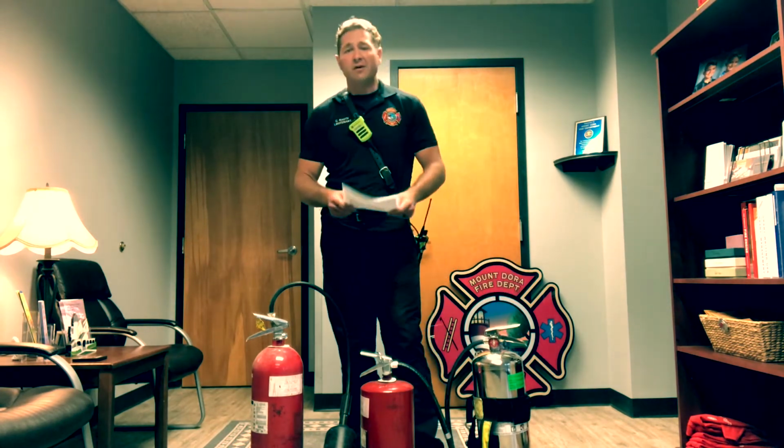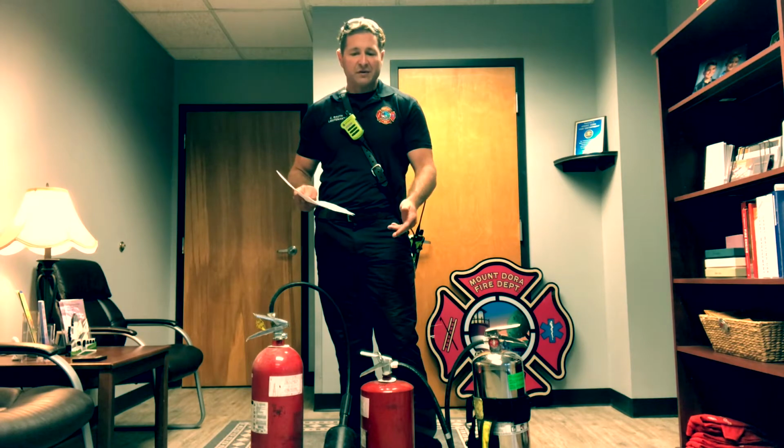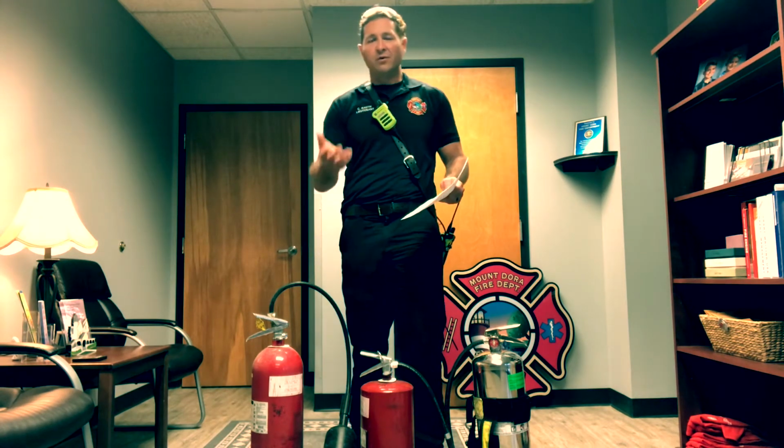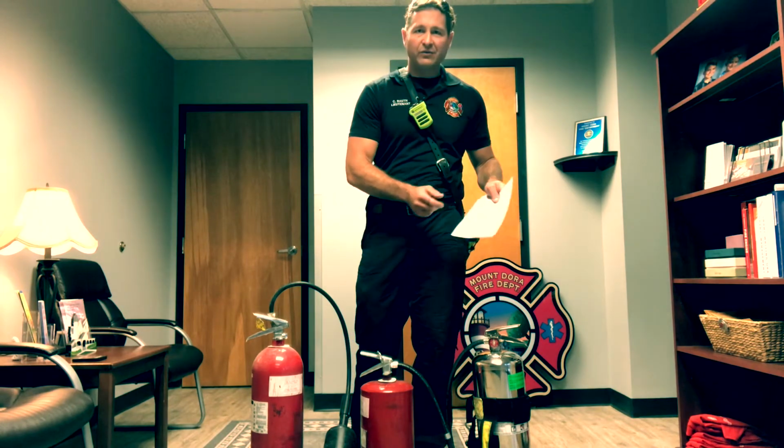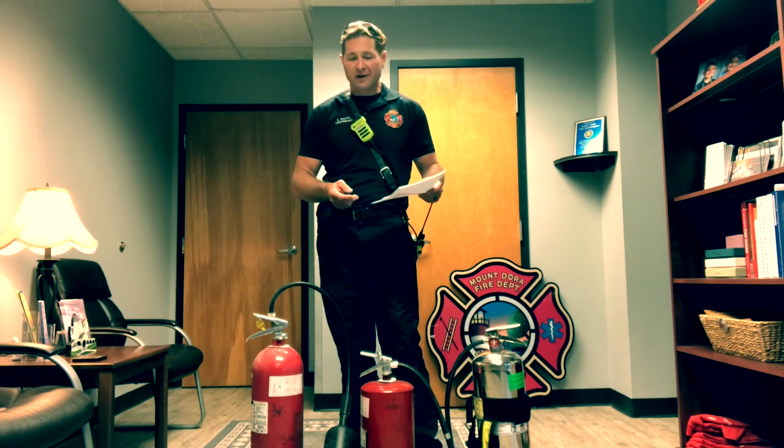If you're extinguishing your campfire or any other combustible material that is not electrified or involves a combustible liquid, then a Class A extinguisher is appropriate. Now, you don't want to use water on a combustible liquid, as the liquid will float to the surface and continue burning, and then it's simply spread around. A Class A water can extinguishes fire by removing the heat aspect of the fire triangle, thereby lowering its temperature below which it will not off-gas anymore and continue burning.